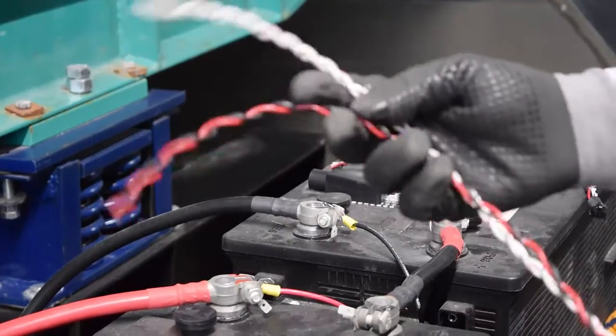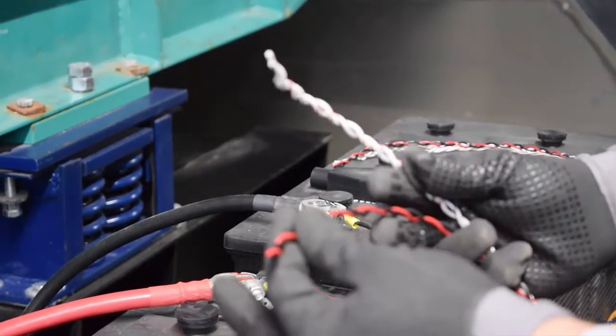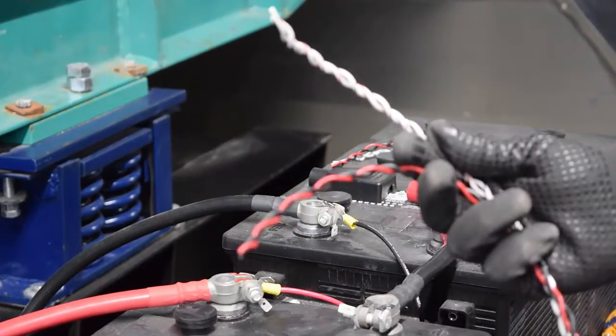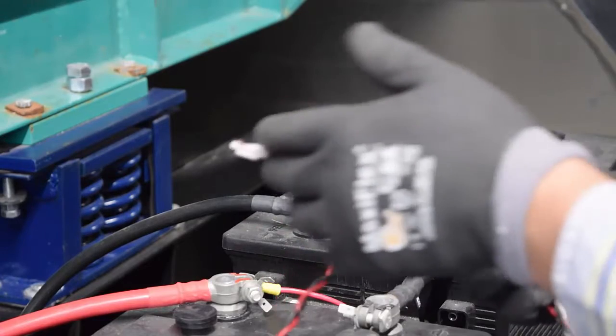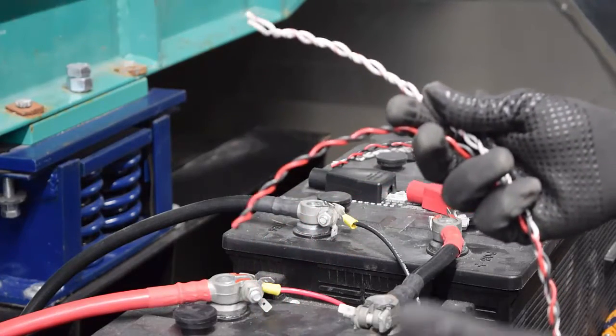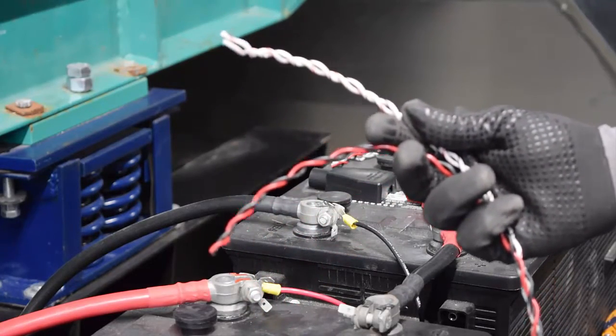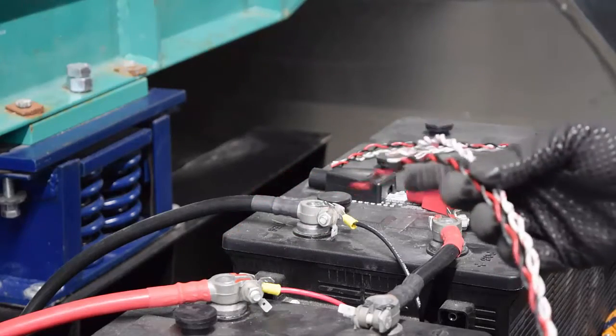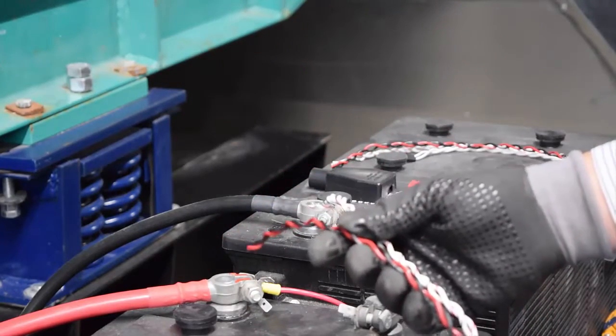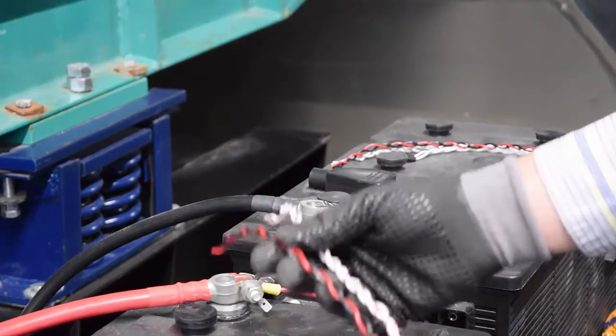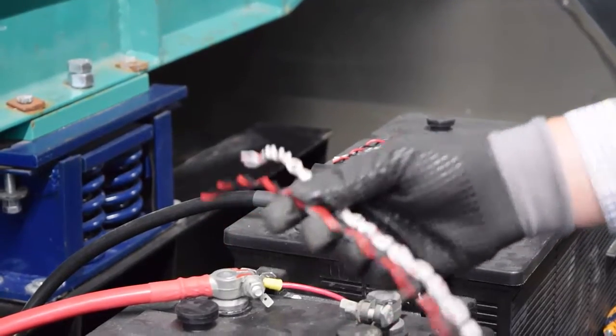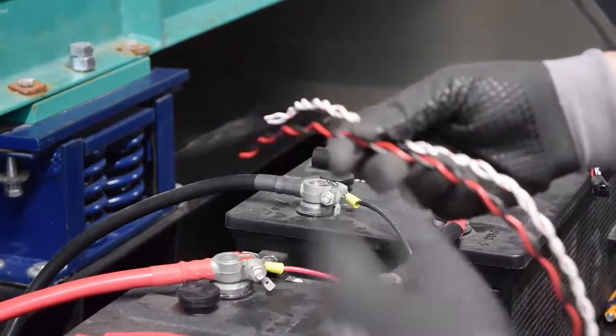Now, the cable harnesses are shipped unterminated. This provides flexibility of installation because you can shorten the leads as needed depending on how and where the VTZ modules get mounted. So once you determine the VTZ cable assembly length you need for your system, measure and cut the power and sense leads to that length.